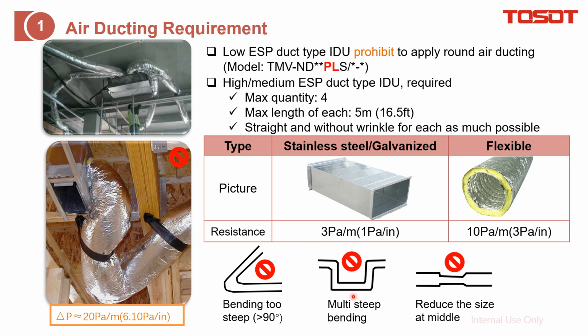Meanwhile, this ductwork also should not change too much, just like this. Not allowed, and also not allowed. This reduces the size in the middle, also not allowed. The reason is this will increase the pressure loss and you will lose air volume.